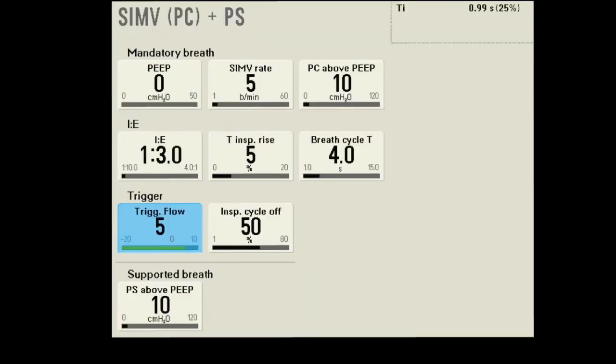As mentioned, I'm going to compare optimal targeting with set point targeting. Now here's a slide of SIMV pressure control. If we were to classify this, even though the manufacturer says the mode's this, if we look at the basic components of the mode, it's going to be pressure control, IMV, and then the targeting scheme it uses is set point and set point. The set point is for the mandatory breath, and the set point targeting is for the spontaneous breaths also.